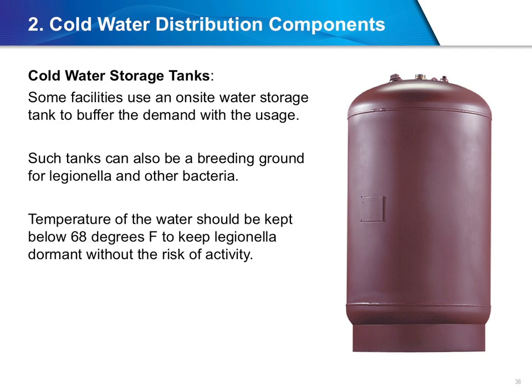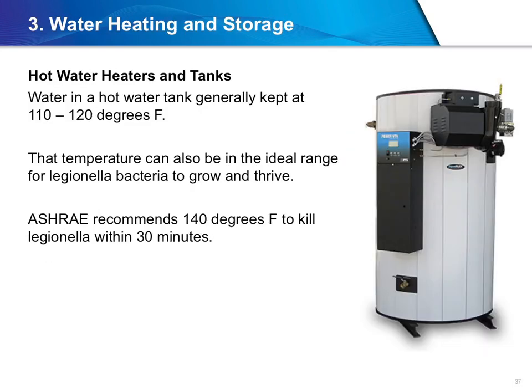Therefore, the temperature of the water should ideally be kept below 68 degrees Fahrenheit to keep Legionella dormant without the risk of activity. Water in a hot water tank is generally kept at an appropriate temperature for warm or hot water use in a building at around 110 to 120 degrees Fahrenheit. Unfortunately, that temperature is also in the ideal range for Legionella bacteria to grow and thrive. If the temperature hasn't been appropriately raised to the ASHRAE recommended 140 degrees Fahrenheit to kill Legionella within 30 minutes, there is the risk of bacteria growth. This will need to be addressed and monitored.